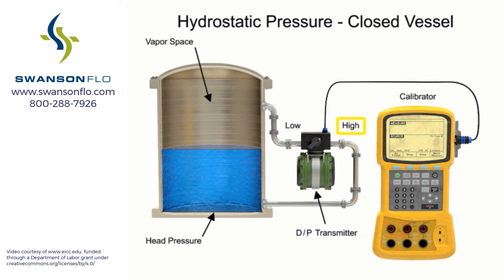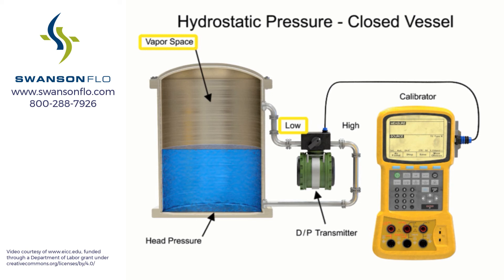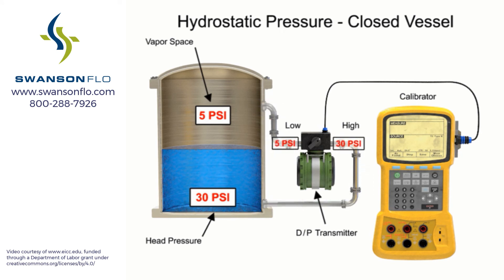This device has a high-pressure side input and a low-pressure side input. The high-pressure input is connected to the bottom of the tank to measure hydrostatic pressure, while the low-pressure input is connected to the vapor space pressure. The transducer subtracts the vapor pressure from the high pressure, resulting in a value that represents the hydrostatic head proportional to the liquid level.